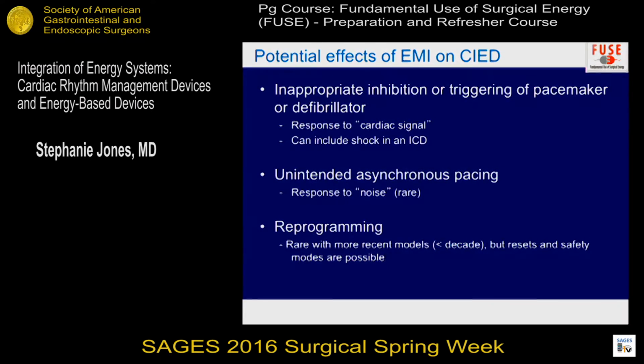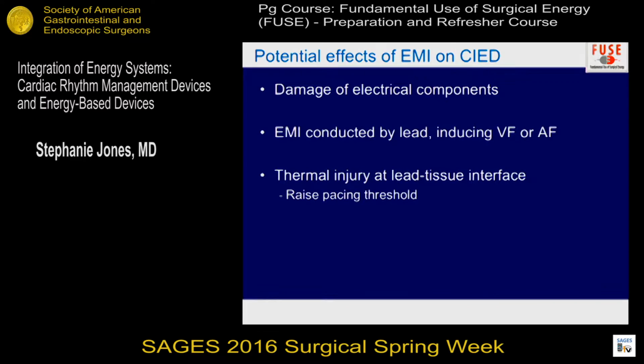reprogramming, though again, not particularly common in newer devices. You can directly damage electrical components if you're close enough. Again, hard to do, hard to damage the pacemaker generator itself unless you're very close with your energy source. You can directly conduct the electricity through the lead to induce VFib or atrial fibrillation. And again, by conducting energy, you can potentially have thermal injury damage at the lead tissue interface. And that's something that's going to present probably a couple days or more after the procedure, so it may be an issue where the patient is not getting their appropriate stimulation by their pacemaker because you now have scar tissue actually in the cardiac tissue.